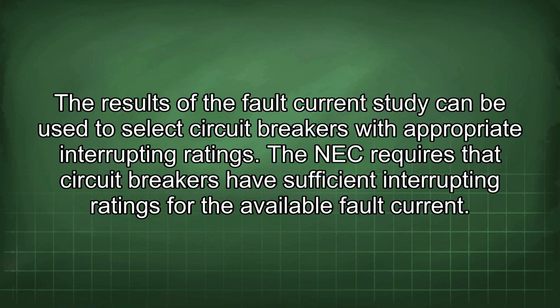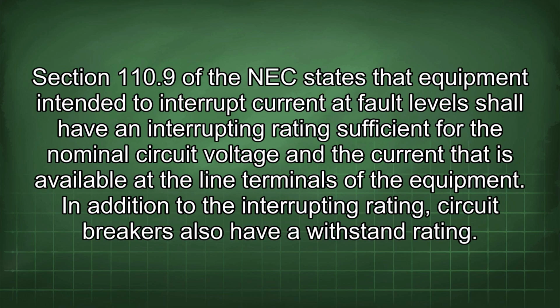The NEC requires that circuit breakers have sufficient interrupting ratings for the available fault current. Section 110.9 of the NEC states that equipment intended to interrupt current at fault level shall have an interrupting rating sufficient for the nominal circuit voltage and the current that is available at the line terminals of the equipment.